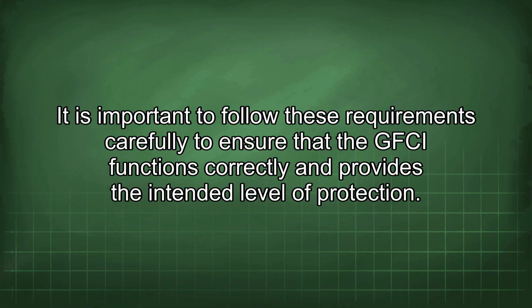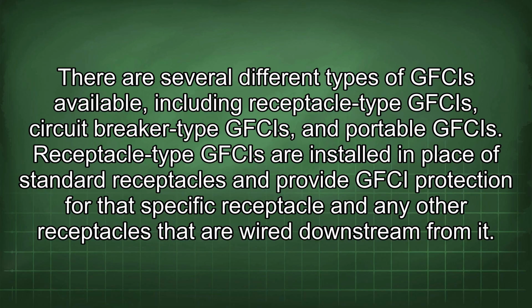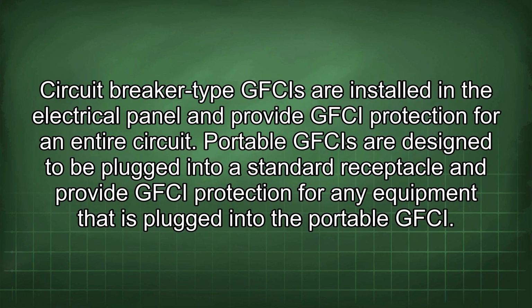There are several different types of GFCIs available, including receptacle-type GFCIs, circuit breaker-type GFCIs, and portable GFCIs. Receptacle-type GFCIs are installed in place of standard receptacles and provide GFCI protection for the specific receptacle and any other receptacles that are wired downstream from it. Circuit breaker-type GFCIs are installed in the electrical panel and provide GFCI protection for an entire circuit. Portable GFCIs are designed to be plugged into a standard receptacle and provide GFCI protection for any equipment that is plugged into the portable GFCI.